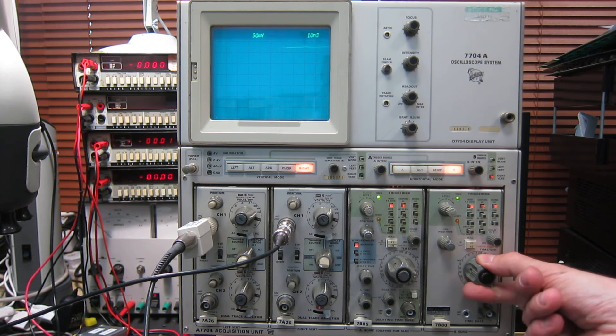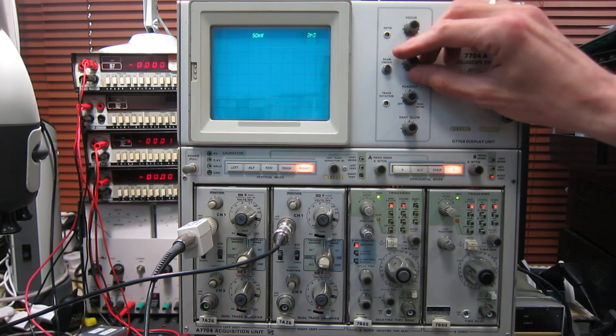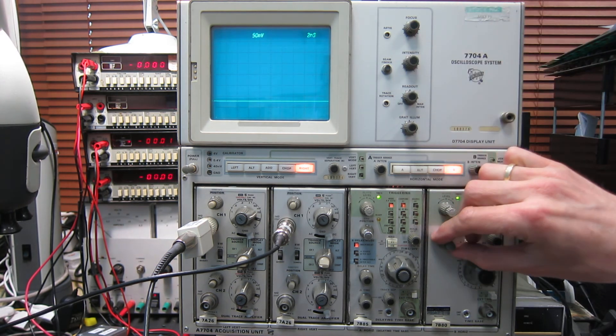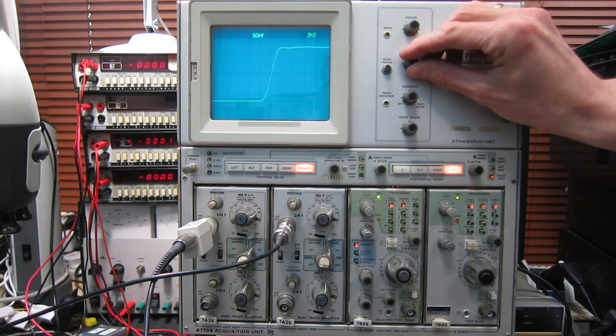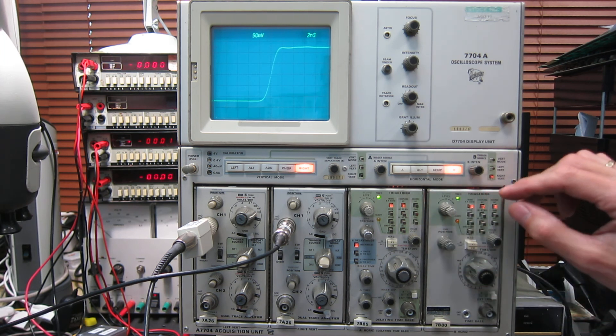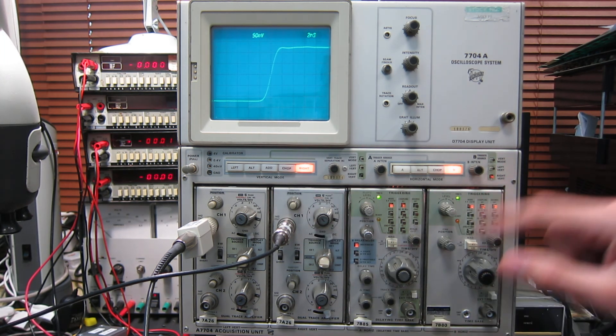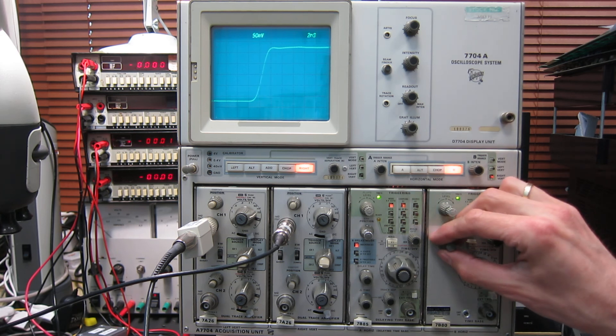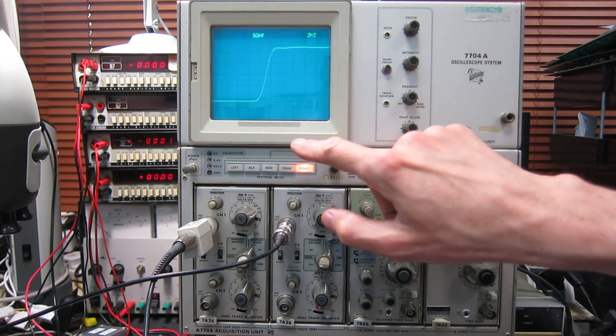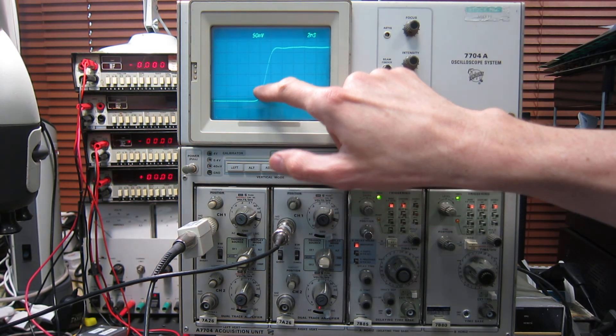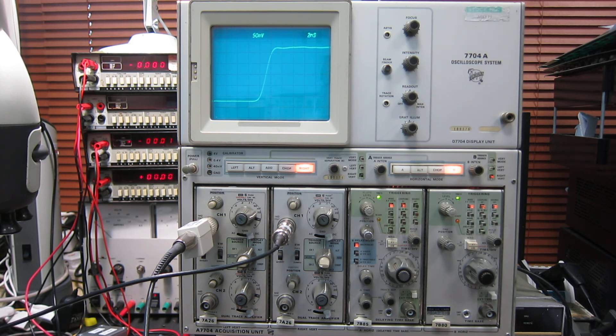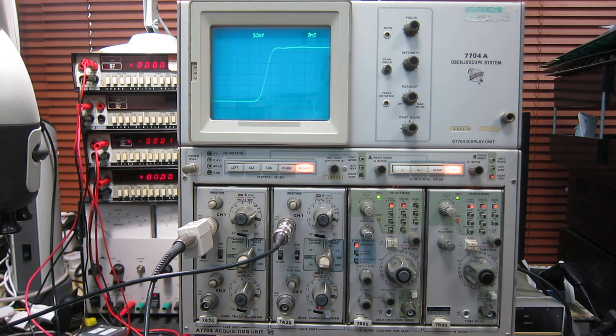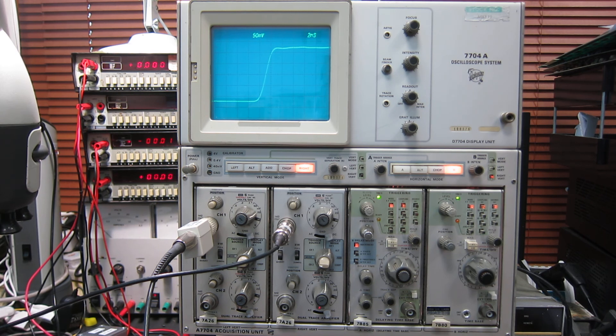So again we'll go all the way to two nanoseconds per centimetre, and we have to crank up the intensity to see it. But this is a fast input signal through the plug-in, so it shows the bandwidth of the whole scope system. Again, if I line that up against the markers here, you can see 10% to 90% is happening in almost exactly two nanoseconds, maybe a whisker less. So that's a bandwidth of around 180 megahertz or thereabouts, which is again well within the spec for this particular mainframe with this particular plug-in.